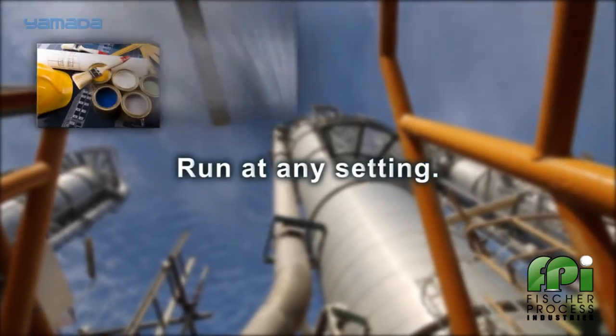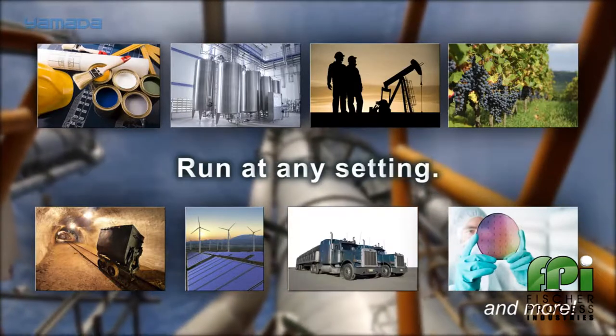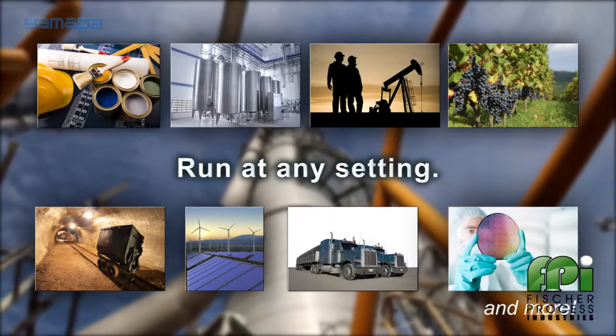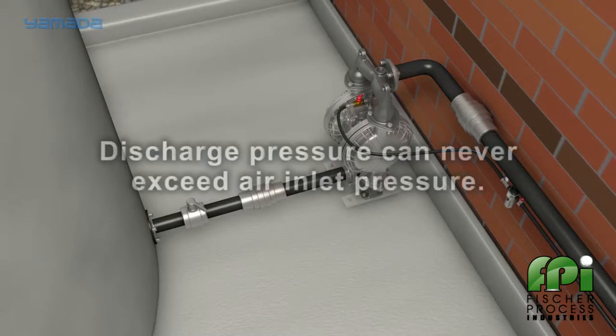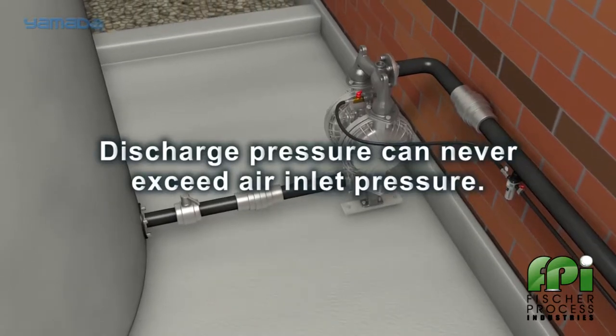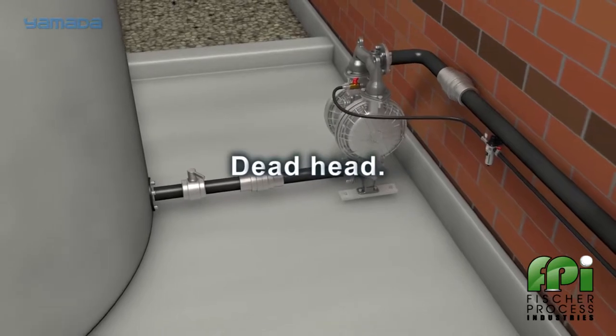Yamada pumps can run at any setting within their operating range simply by adjusting the air inlet pressure. That means one pump can fit a broad spectrum of applications. Yamada pumps can be easily transported and installed. Simply connect the air supply and liquid lines and your pump is ready for use. Discharge pressure can never exceed the air inlet pressure, so the discharge line can be closed with no damage or wear to the pump. We refer to this as deadhead.